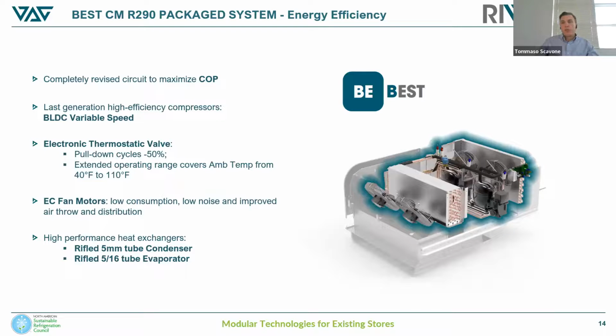The circuit of this monoblock has been completely revised, with the target of maximizing the COP, practically increasing the cooling capacity, and at the same time lowering energy consumption in all working conditions. The range fits BLDC variable speed compressors of the latest generation that allow energy savings up to 15% compared to our previous R290 monoblock system, and up to 40% compared to a 4-4 package system.